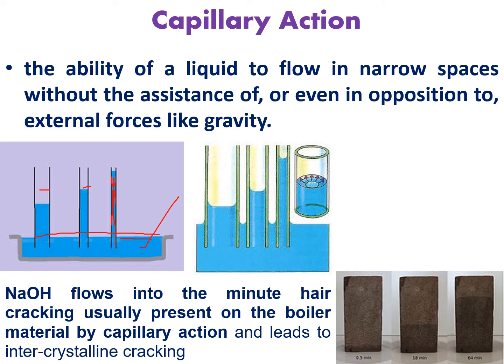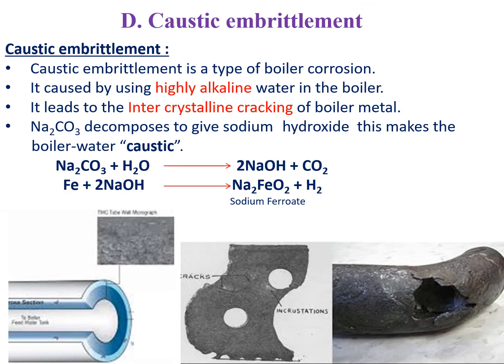Every metal has a porous texture — small minute holes on the surface. Boilers also have many such porous textures. If the water contains NaOH, that water has capillary action and will enter into these minute hair cracks, leading to intercrystalline cracking. This intercrystalline cracking is called caustic embrittlement, and it is also a type of boiler corrosion. It is very dangerous compared to regular boiler corrosion — while boiler corrosion due to O2, CO2, and mineral acids occurs on the surface, caustic embrittlement occurs internally.